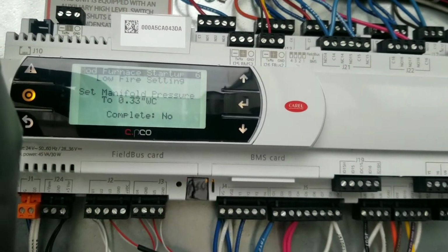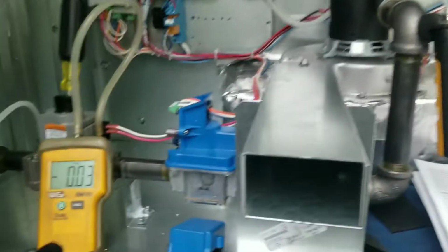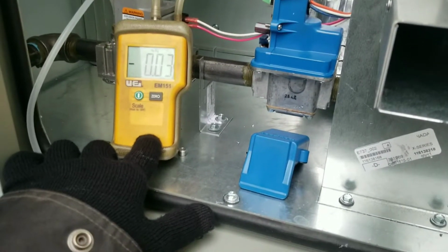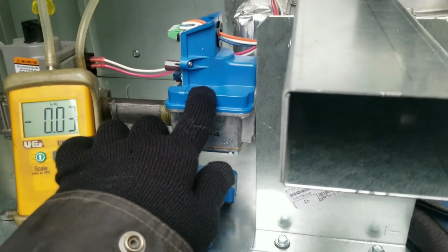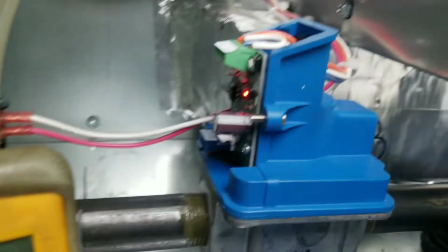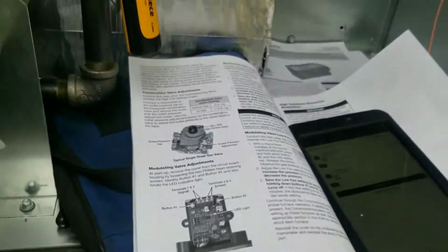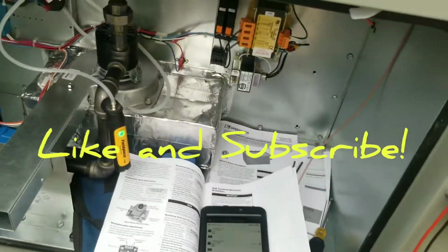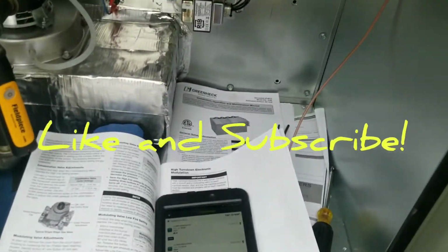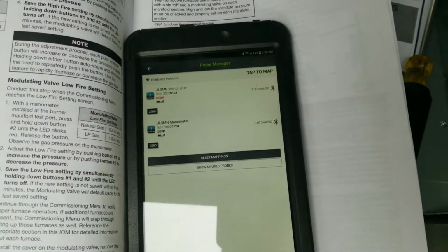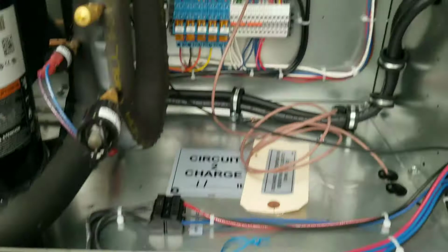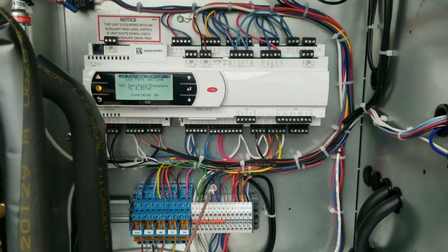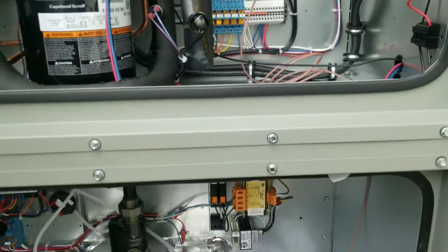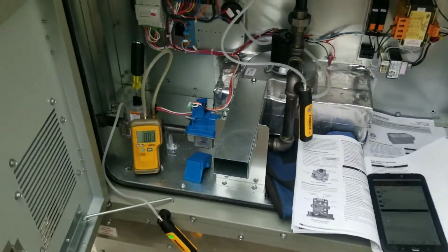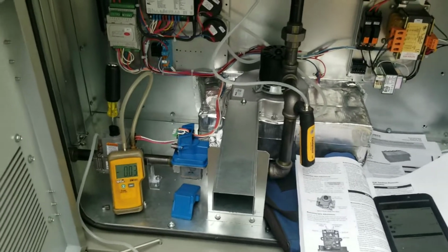Was in low fire, so 0.33, and basically we give it 5 inches of water column out of here. So we adjusted that, then you adjust high fire and low fire with those buttons on that control. It's kind of interesting. So that's why you always read your book. Everything's a little bit different, and this kind of unit is new to me. So we're gonna watch it cycle again and just go through and verify all of our set points one more time, and then go from there. But that is an interesting valve with a little circuit board on there.